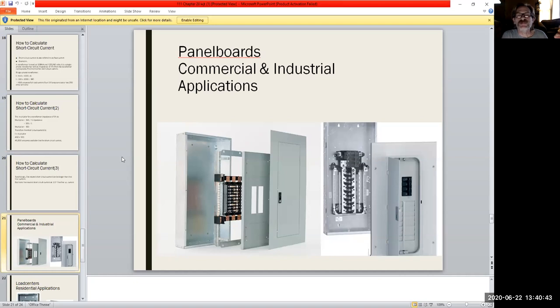But anyway, so typical illustrations of panel boards, commercial, industrial applications. You find that they really don't change much in the way they look from a residential to a commercial to an industrial setting. Sometimes it's the size, like how large physically the panel board is in an industrial setting, just because you have more things going on, more branches to feed and things like that. But as far as the size and shape and whatnot, they're pretty consistent.